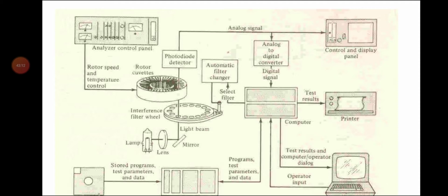When this radiation passes onto the sample, the sample absorbs some of the radiation. The remaining radiation exits from the sample onto the detector. This is the transmittance of the radiation observed by the detector. The detector is usually a photocell or photomultiplier tube.